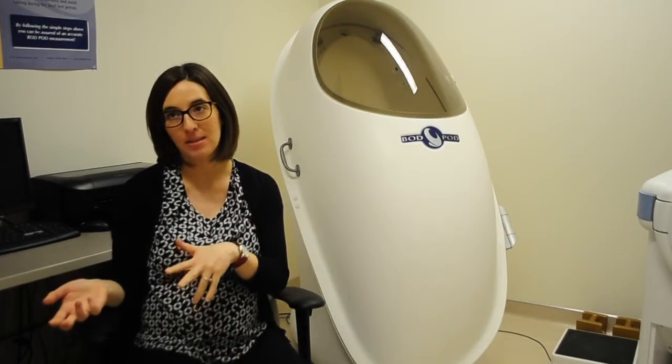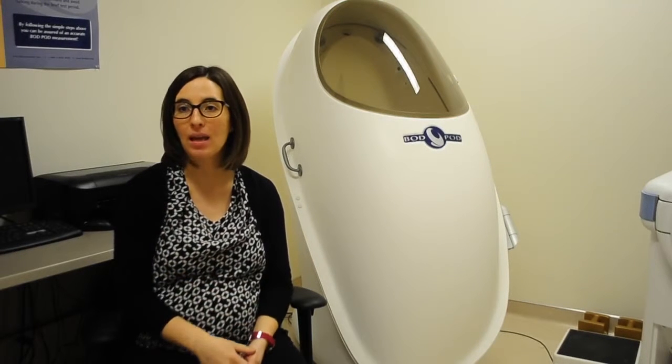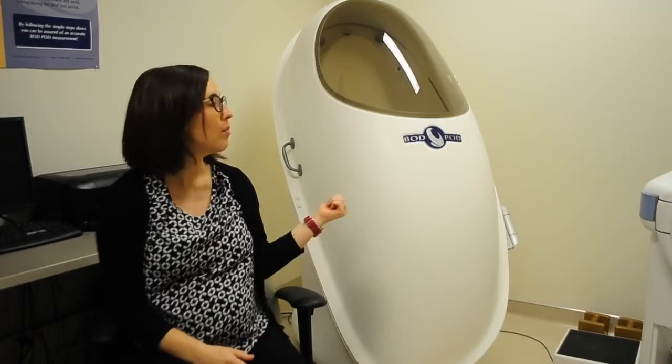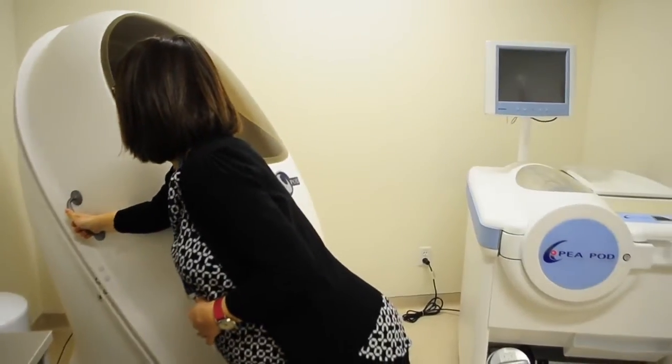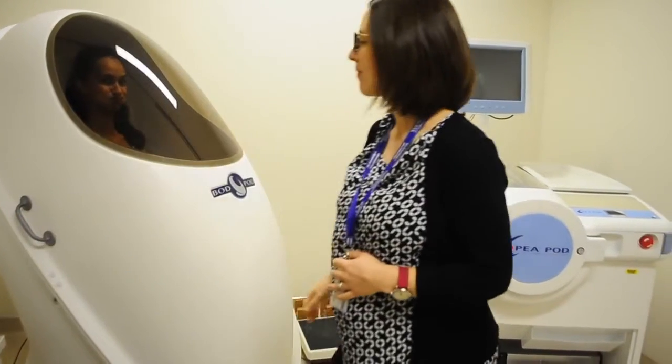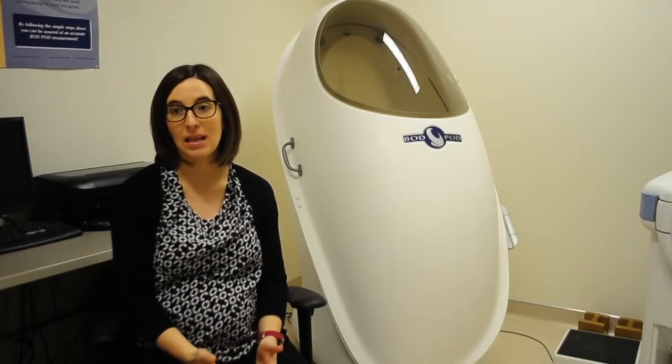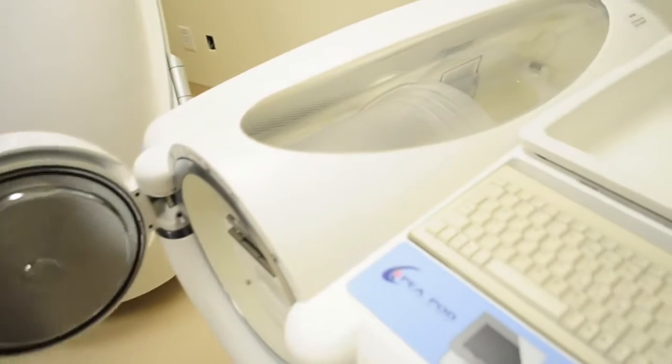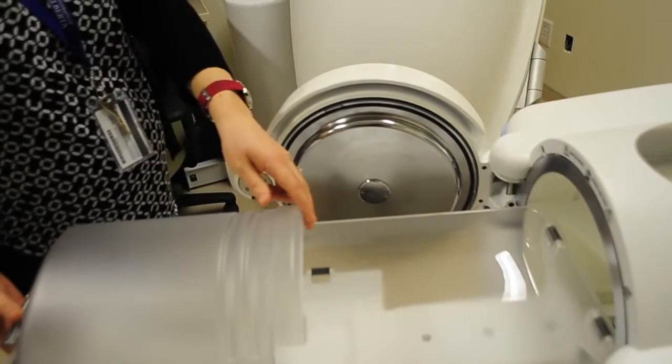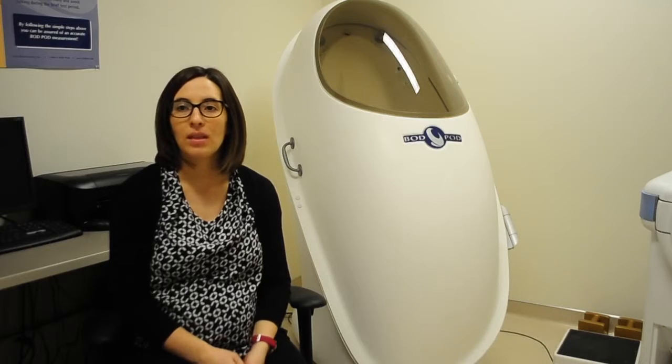The way that the Bod Pod works is that it measures body composition, so it provides an estimate of someone's fat mass and fat-free mass. We measure a person's height and their weight, and then with the Bod Pod we measure their body's volume. We know exactly how much air is contained within the pod, and then when someone sits inside of it, we find out how much air their body displaces from the pod. From that, we're able to figure out what their volume is, and then we have equations that take the height, the weight, and the volume to estimate someone's fat mass and fat-free mass.